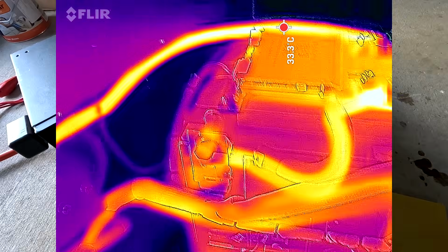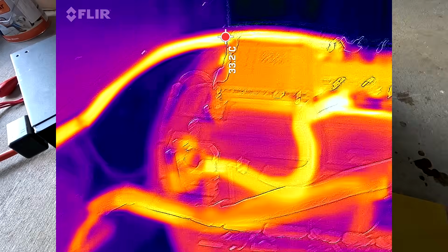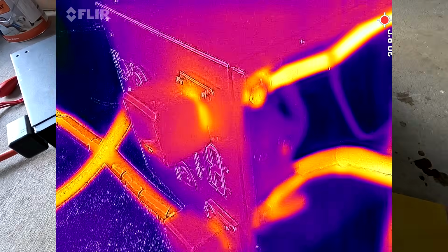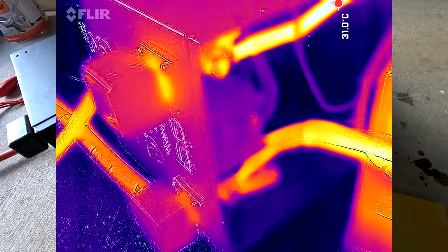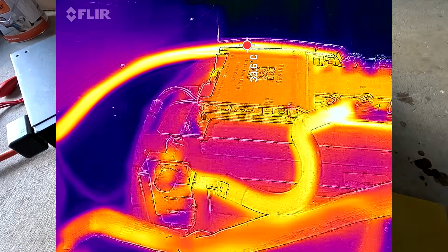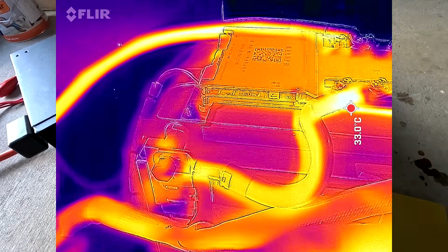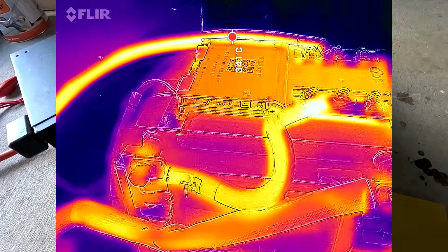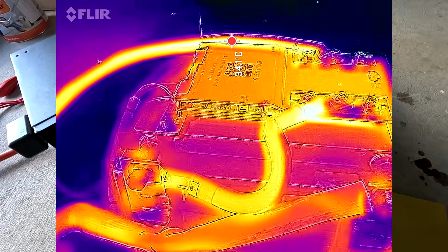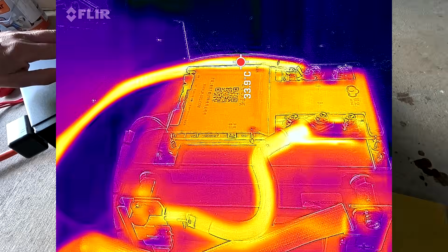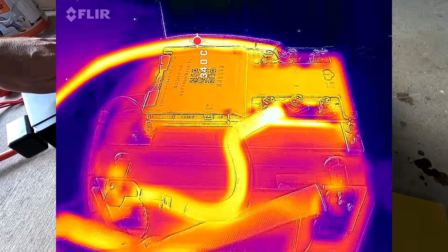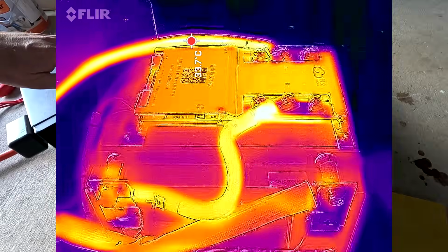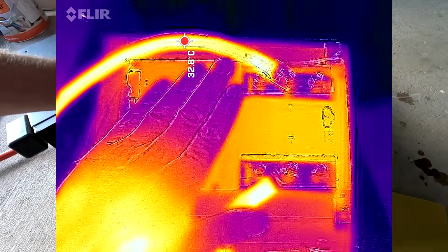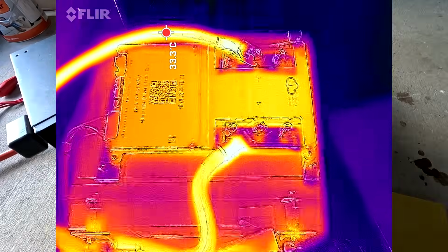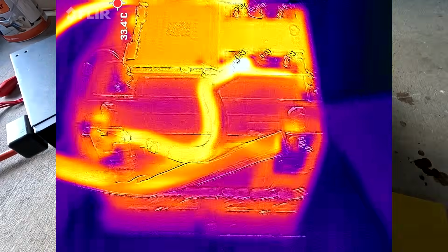I think this is the configuration I would run the battery with, connecting everything directly to the M10 terminals on the outside, and having the inverter do all the work. So far everything looks good at 150 amps. I don't think there are any thermal issues. It may look a bit different in summertime when it's already 35 degrees outside, but the usage of this battery with this load is very limited, because the electric chainsaw and garden shredder aren't constantly running at full power. So I don't think we have any problems. BMS is nice and cool, and it runs only on 50% of capacity anyway, so that's all good.